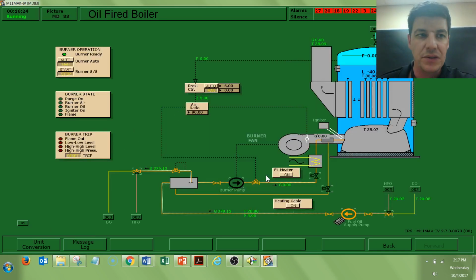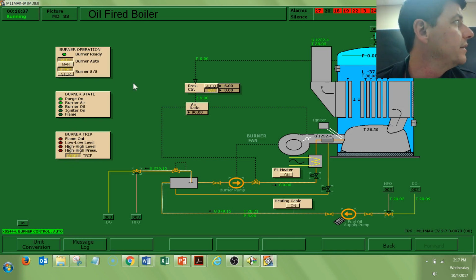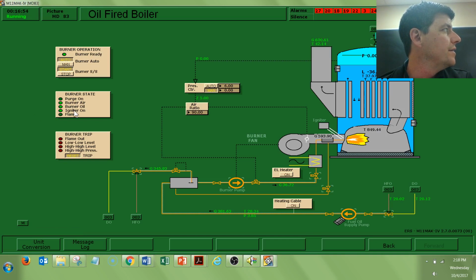I think I'm okay to light my boiler. I even have my burner operation light in ready. Sometimes if you have a trip showing, you may need to reset. But getting this guy into auto, he's going to automatically turn himself on and off as needed, depending on the boiler pressure. Purge is happening. Oil's being added in, igniter. And we got flame.